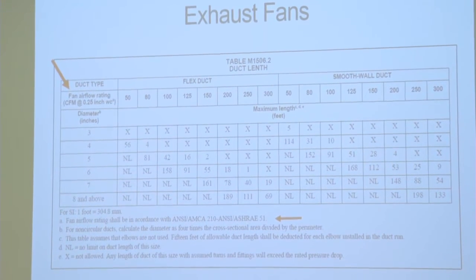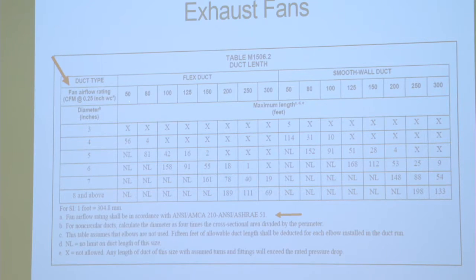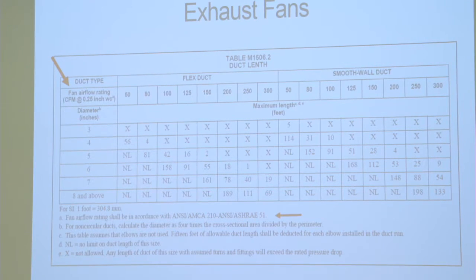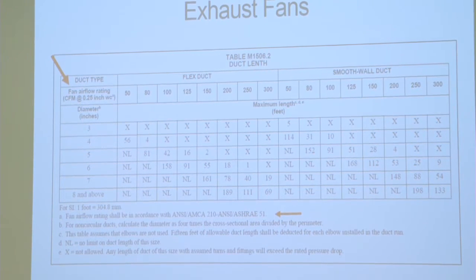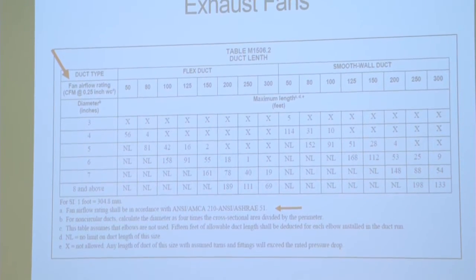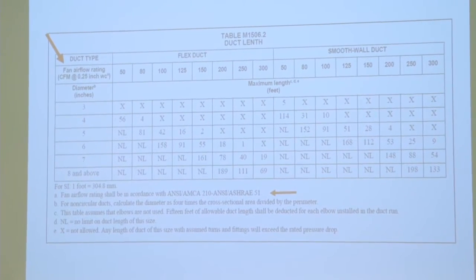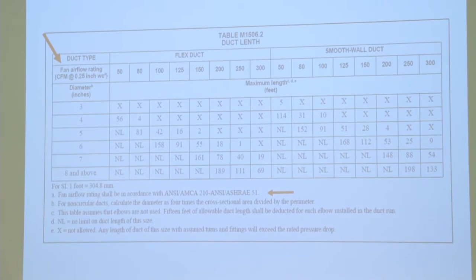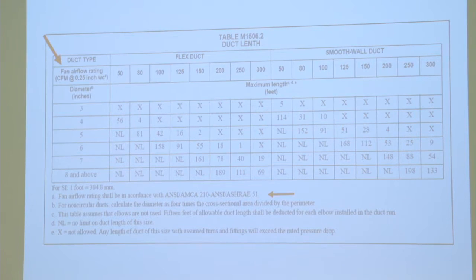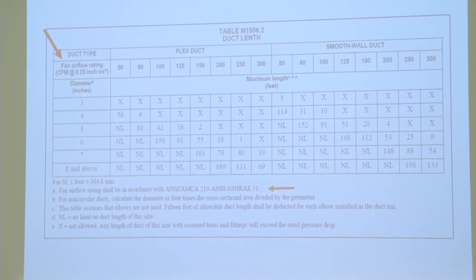So you have a 50 CFM fan or an 80 CFM and you have to move 50, you could put some flex duct on it, but 56 isn't that long, because you have to add up all the elbows in that snake that's running across there. This is in the code. If it's smooth wall pipe, then you can get a little more length out of it.